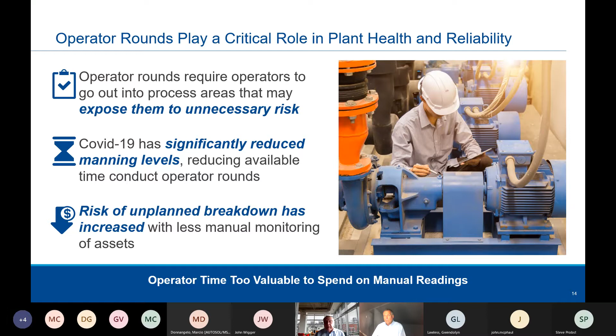This has been particularly important in the last year because we've seen many plants reduce their on-site manning levels, which reduces the time available to conduct manual rounds. We want to do that without increasing the risk of breakdown, so we put in remote measurements that enable us to detect these problems. When you put in these new measurements, you have a continuous measurement of the issue rather than something only occasionally checked with manual rounds.